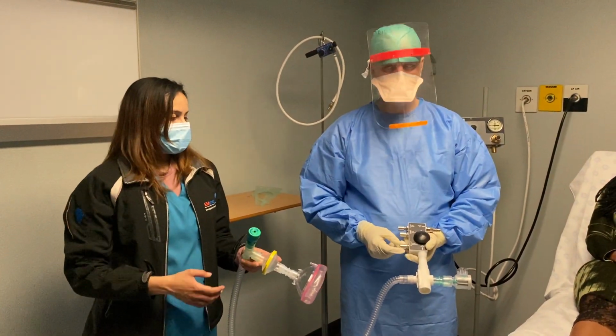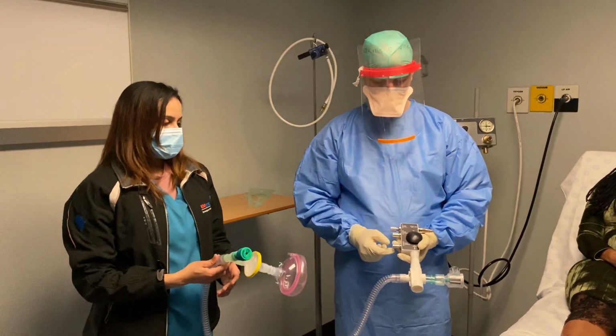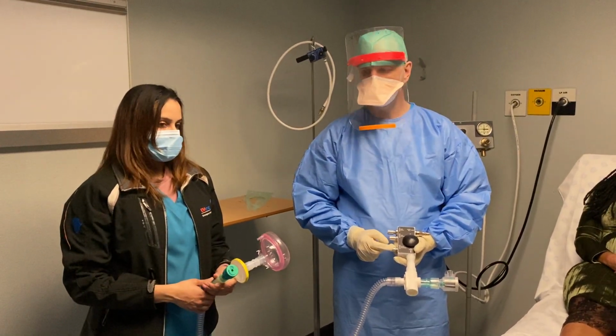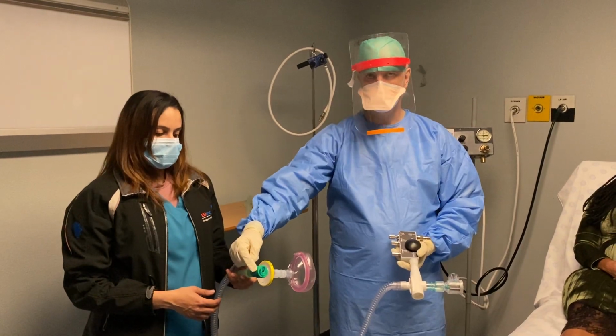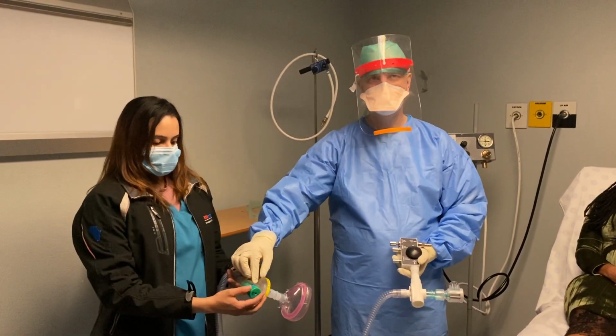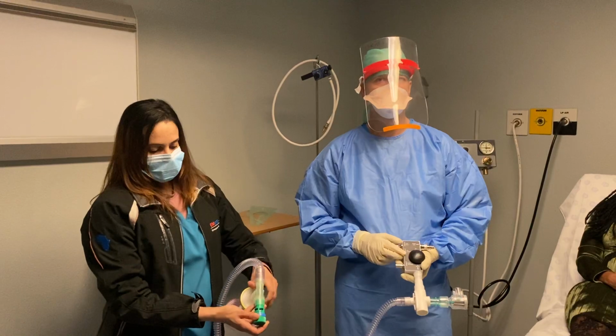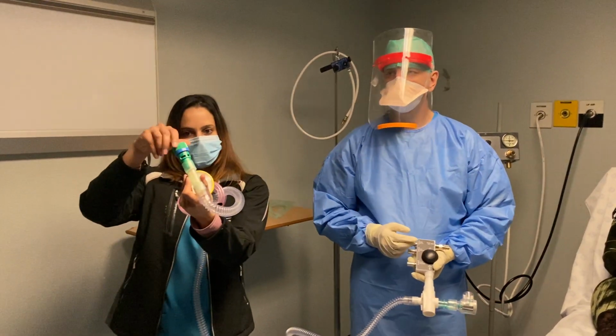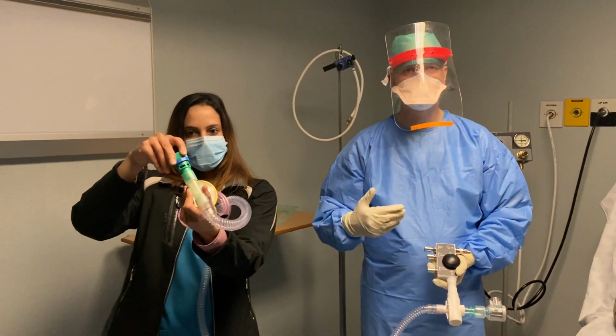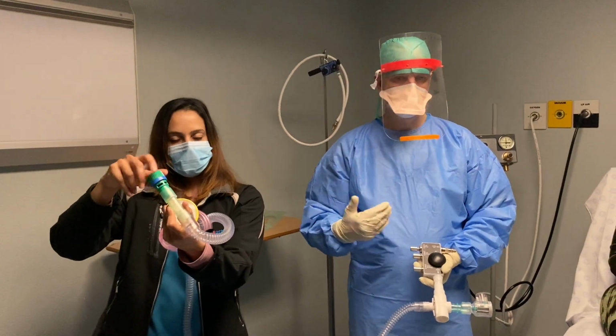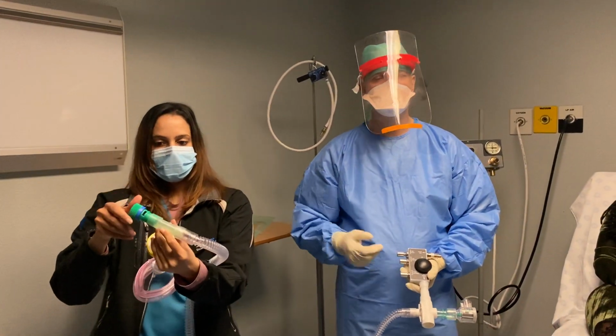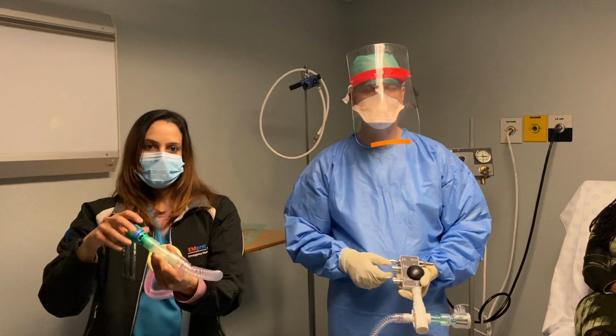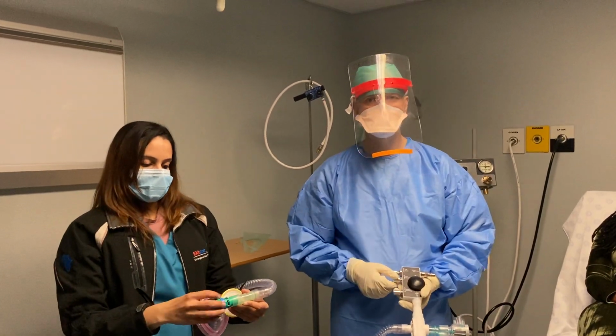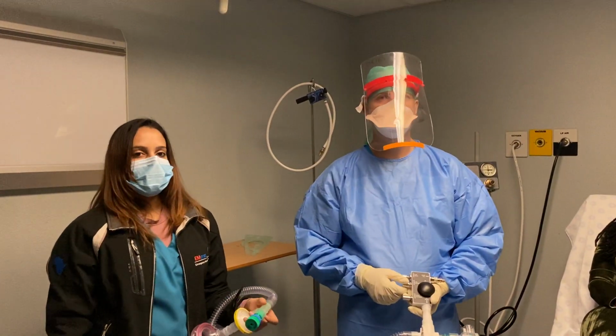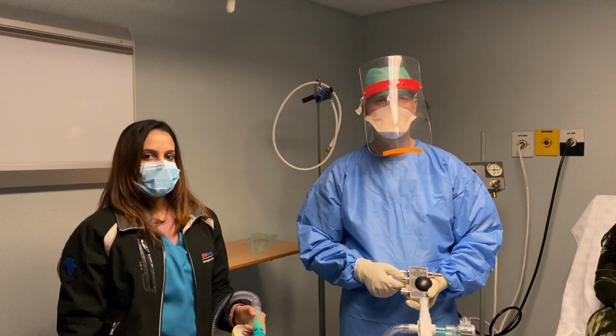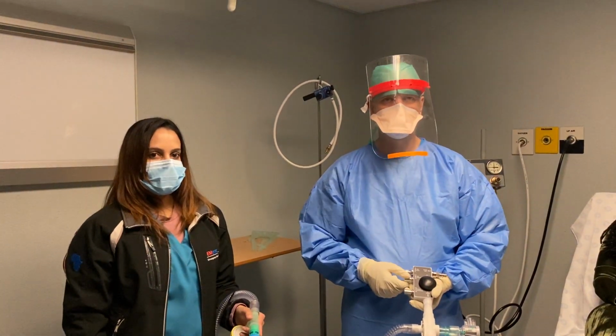The 2 oxygenation tools that all of these devices share is firstly the FiO2 button, and secondly it is the PEEP valve. The PEEP valve can be adjusted to increase the PEEP or CPAP, and it can basically be increased all the way up to 20. But often, if we get to those high levels, it might be the point where the patient actually requires a different or a more advanced ventilator, or actually requires mechanical intubation and mechanical ventilation.